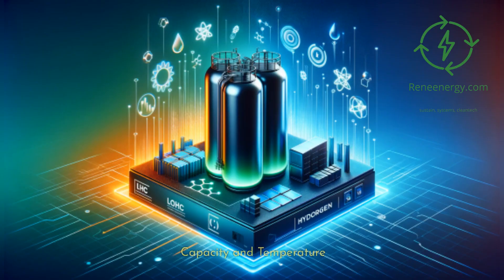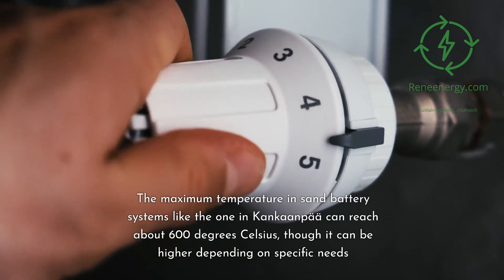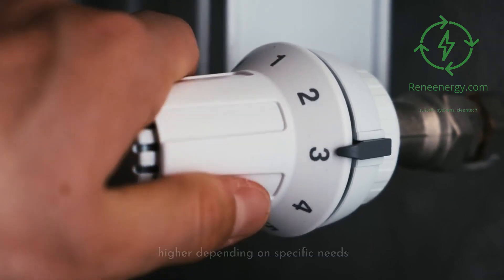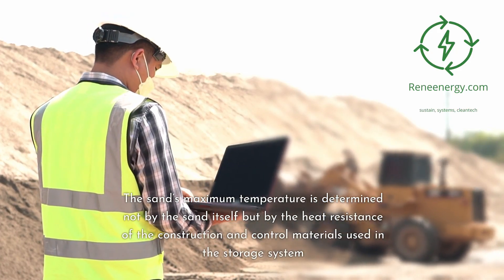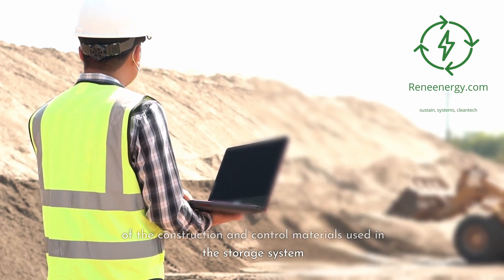Capacity and temperature: the maximum temperature in sand battery systems like the one in Kankaanpää can reach about 600 degrees Celsius, though it can be higher depending on specific needs. The sand's maximum temperature is determined not by the sand itself but by the heat resistance of the construction and control materials used in the storage system.